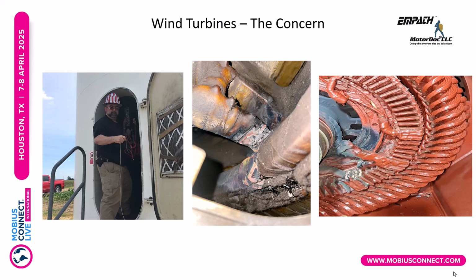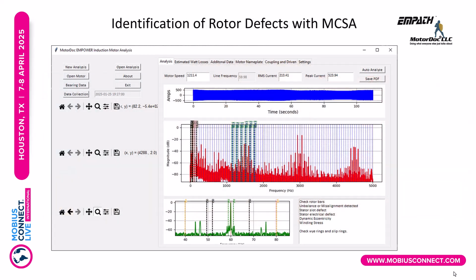Wind turbines, primary concern, blowing up the rotors. So in this case, check rotor bars, you look at the below part in this. They checked the test for wind turbines. So it says check Y rings and slip rings. In this case, this particular machine has a failing Y ring. That is the rotor connection, and you can see it also has a drive associated with it.